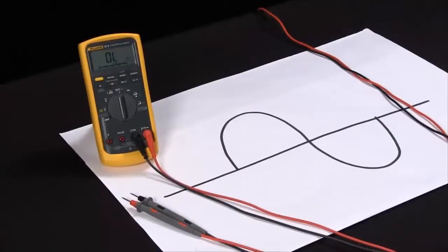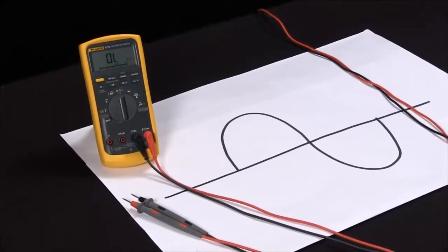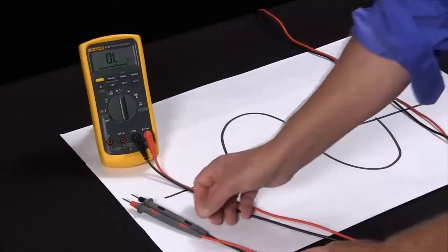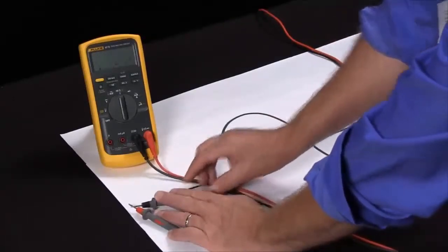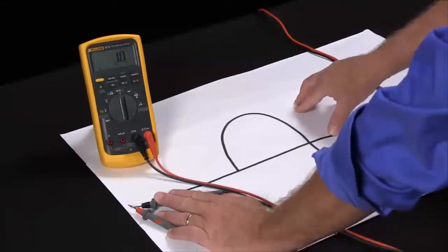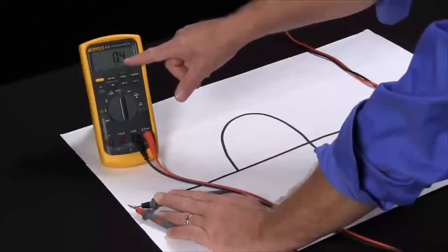We're here to explain the delta or relative function that you'll find on meters, and we're using the Fluke 87V as the example. One of the main reasons for the delta or relative mode is when I have a set of lead resistance on test leads.